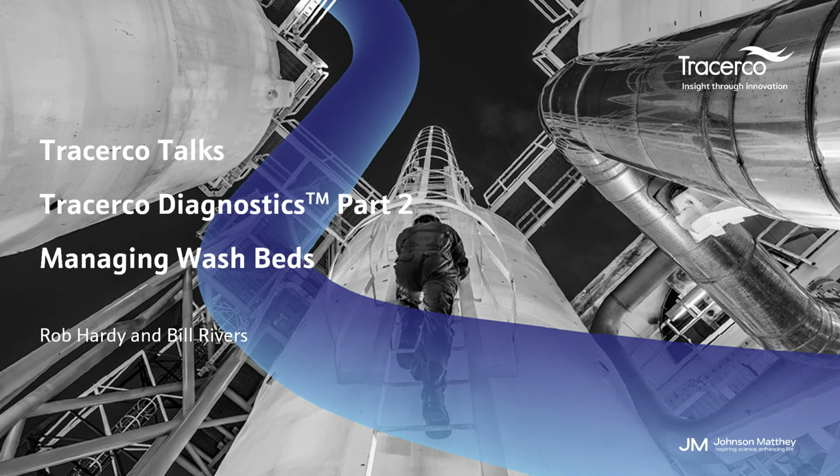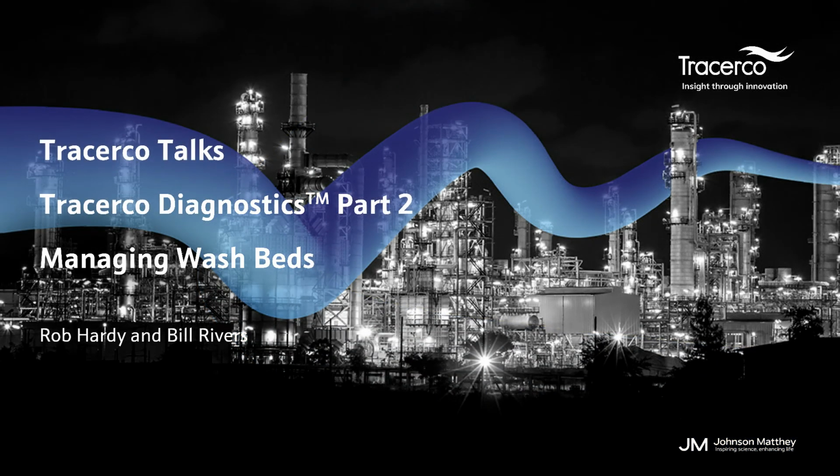What most customers have us do is, when we start these types of programs, we start off with the wash bed completely clean, nothing's happened yet. It's going to be nice and bright blue. Then as we move forward, customers want us to come out once a quarter, once every 6 months, or once a year. We take the same elevation over and over again, and they can compare from quarter to quarter, 6 months, or a year, or whatever their program is. From there, they can manage the growth of the fouling, adjust their operating parameters, or better yet, optimize the process to make it better and more efficient for them.